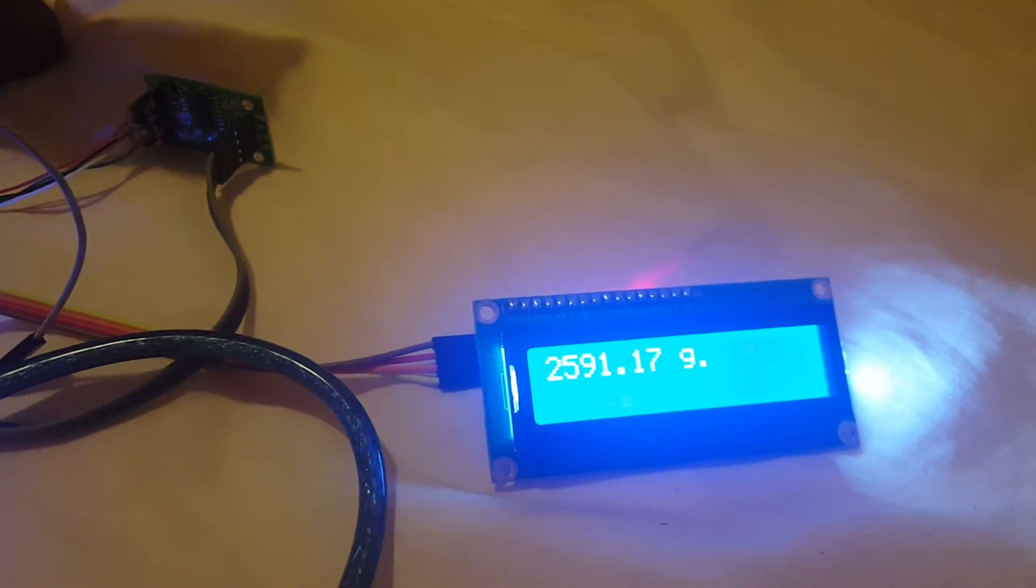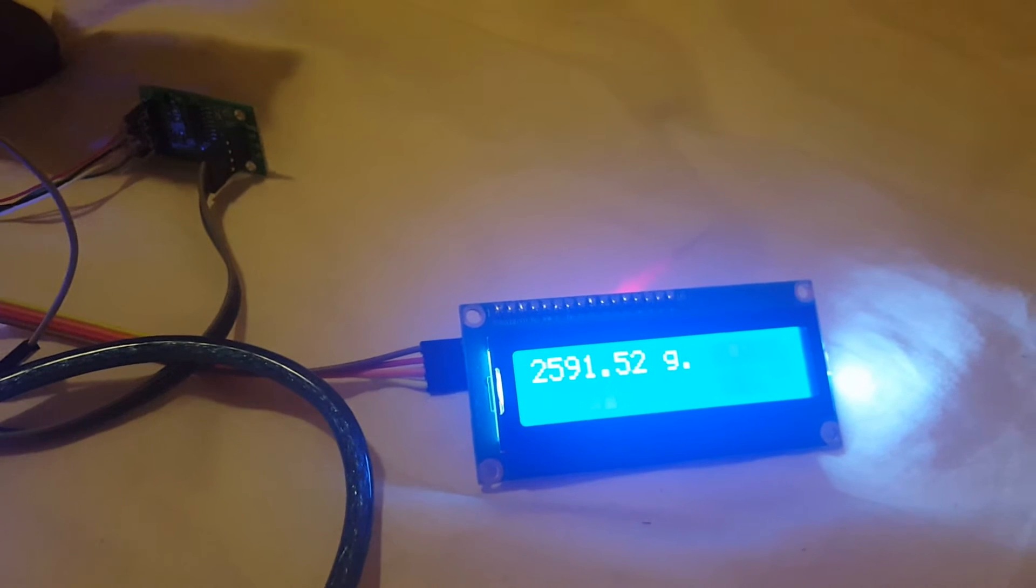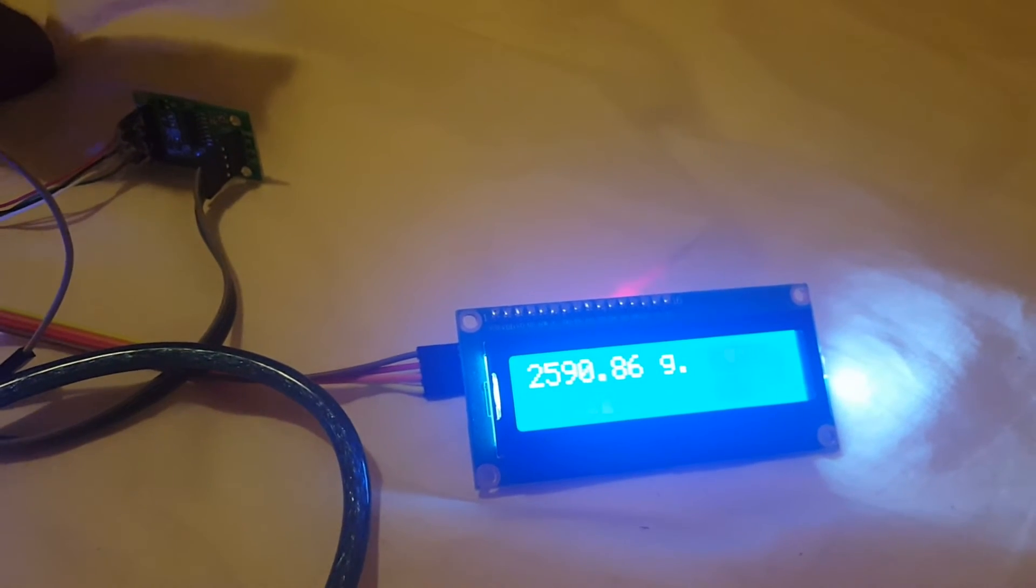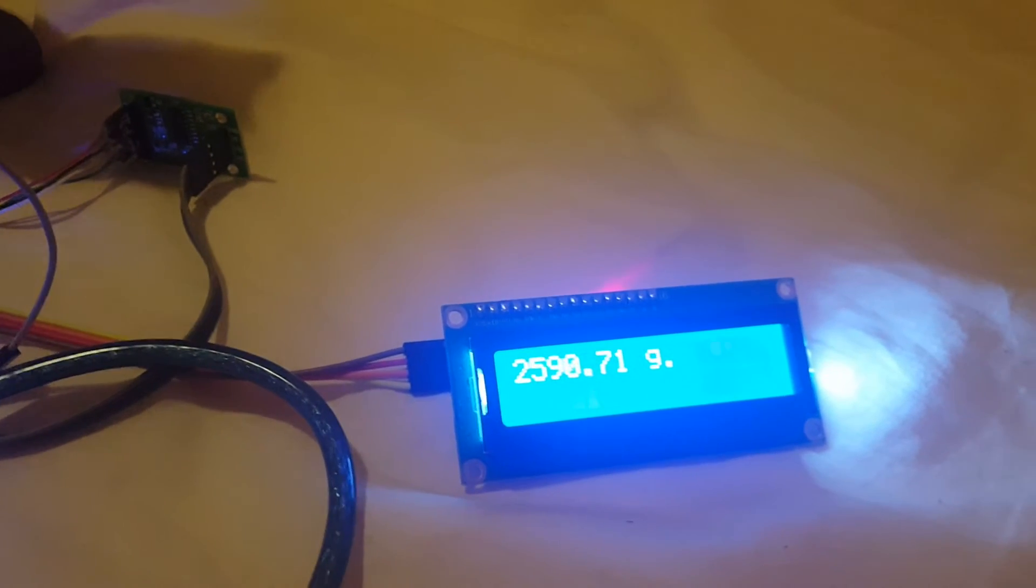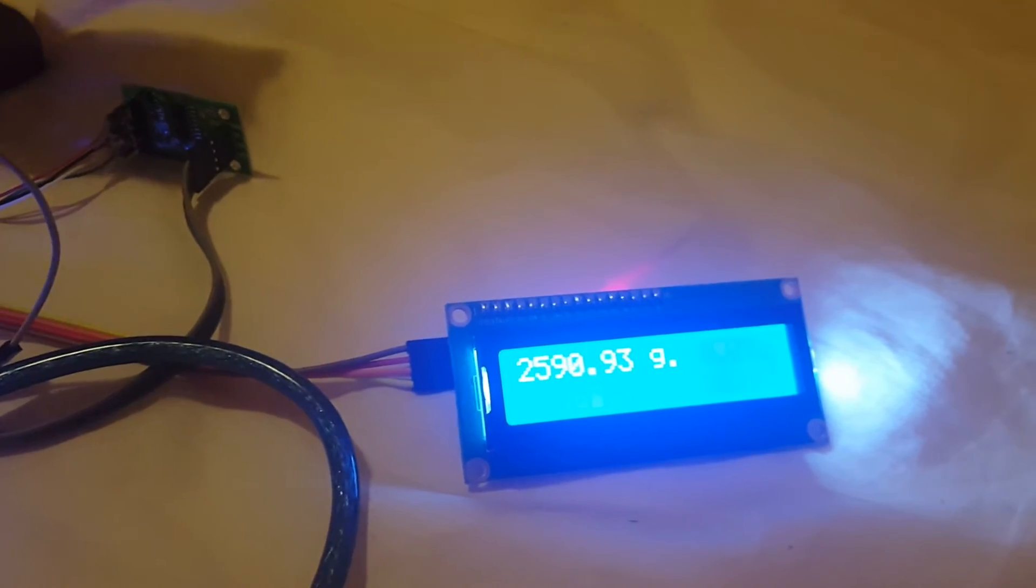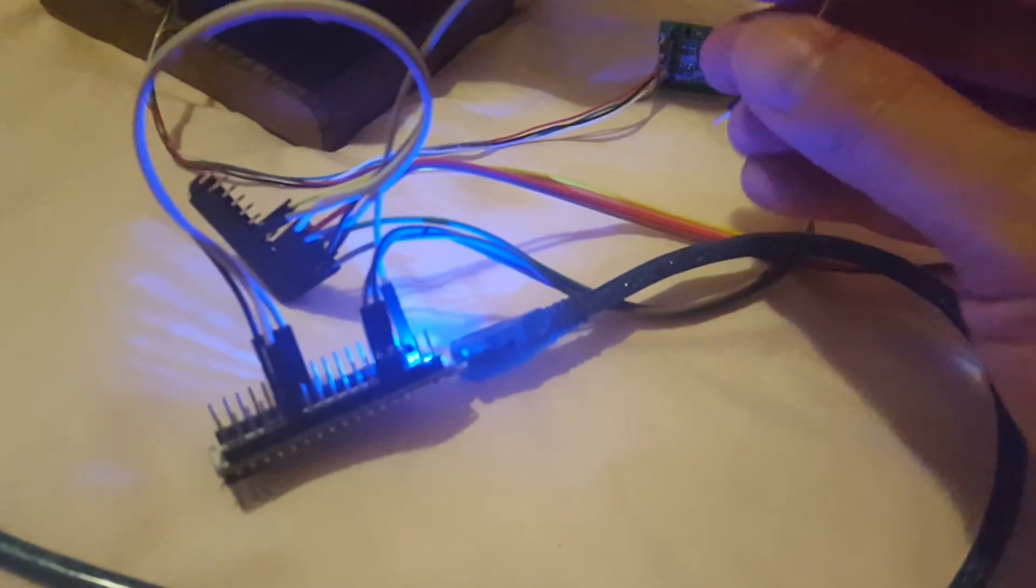You need a much smaller load cell, for example 1 kilogram or something like that. The accuracy will be much better. We have the calibration zero adjust button.